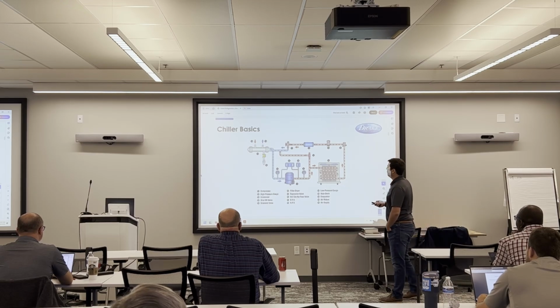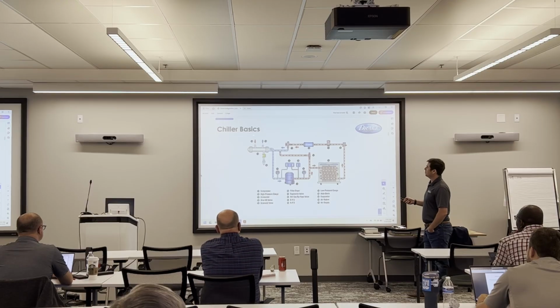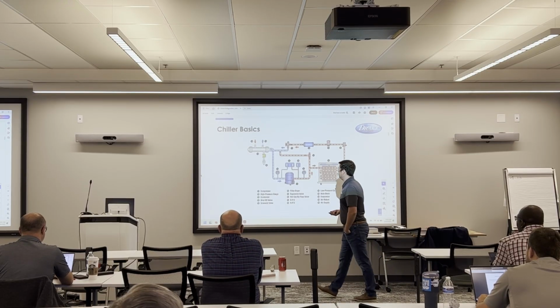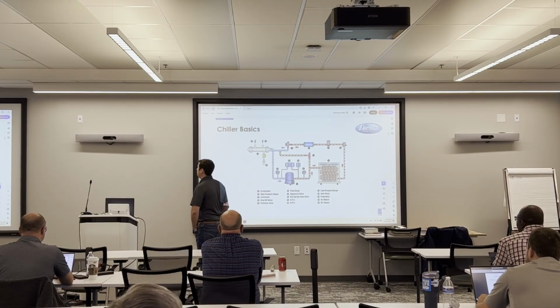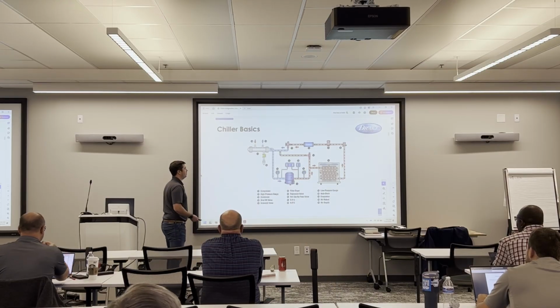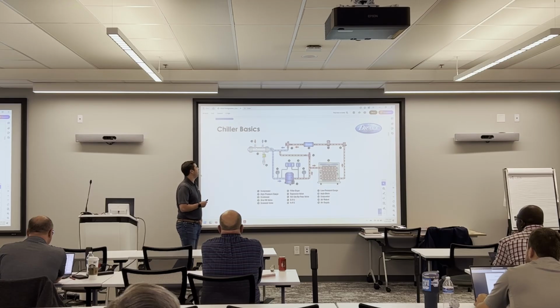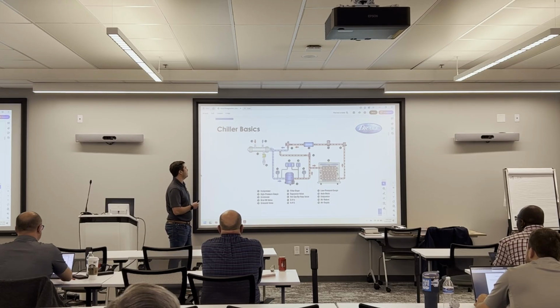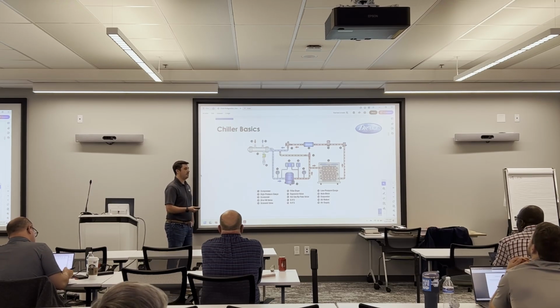On any refrigeration circuit, you're going to have an evaporator. It's your cooling medium for what you're trying to chill. For chillers, we cool fluids. We don't cool spaces. We don't cool air. We're cooling water, a glycol solution, in some cases rocket fuel, depending on who we're working with. So essentially, you'll have a hot fluid coming in. This could be water coming in at say 60 degrees or so. The refrigeration circuit is going to absorb all that heat from the water. The water's going to leave the evaporator cooler, hence being chilled.